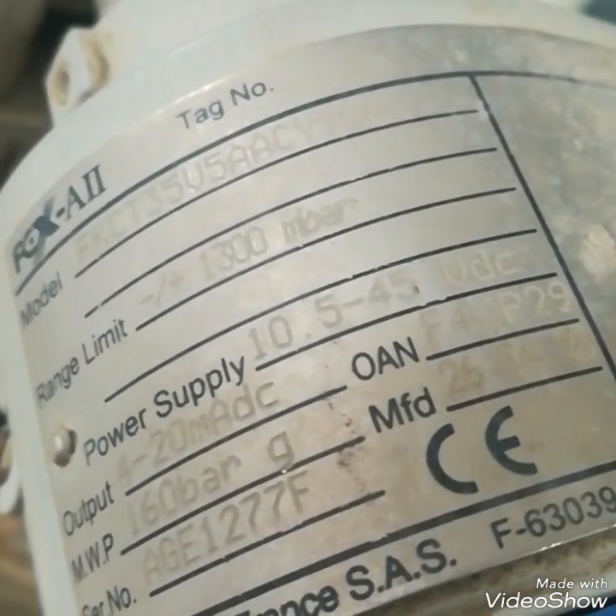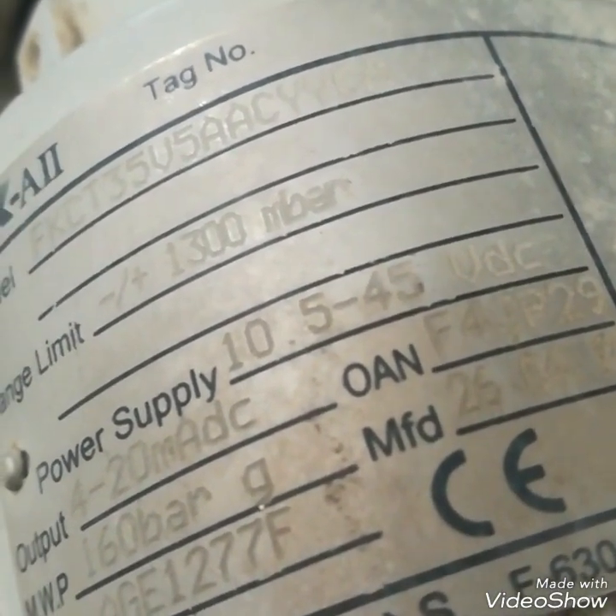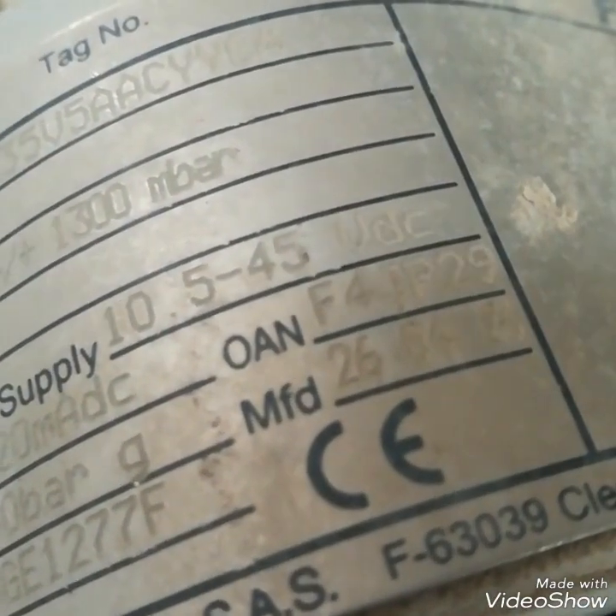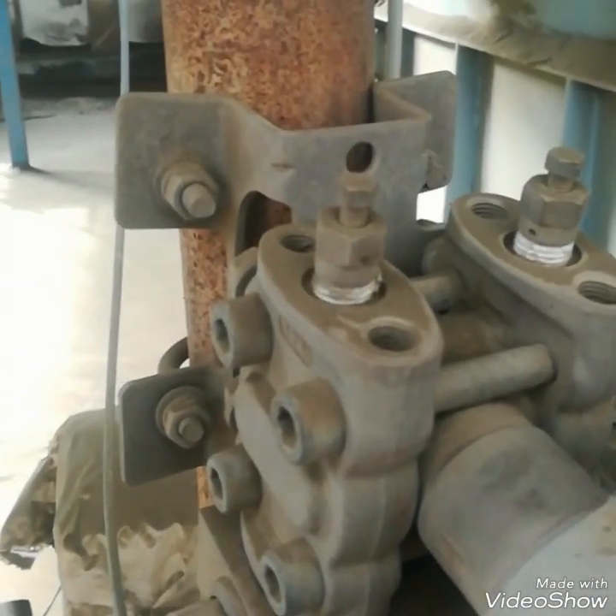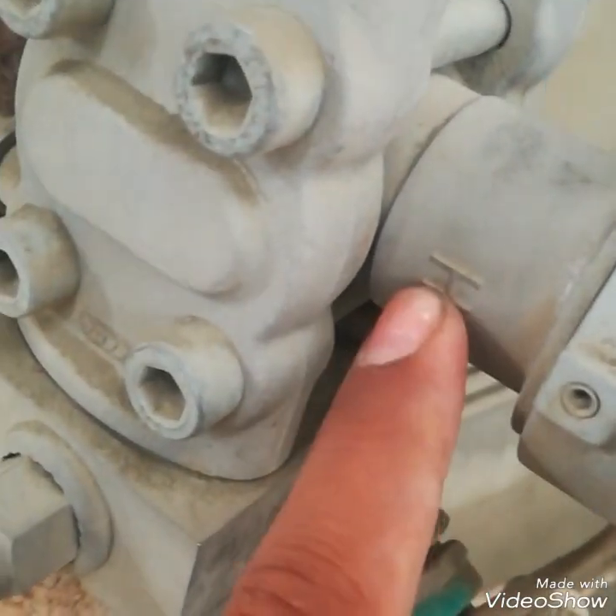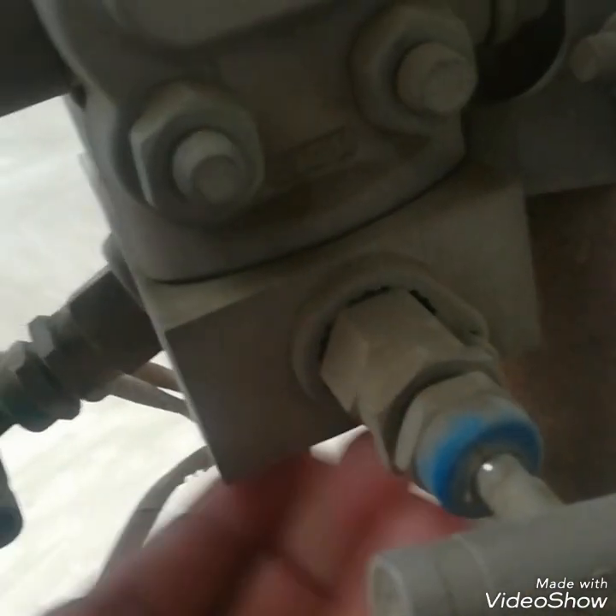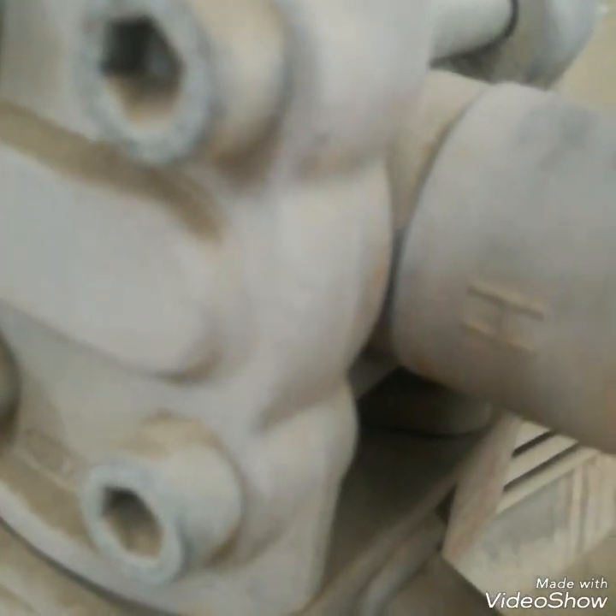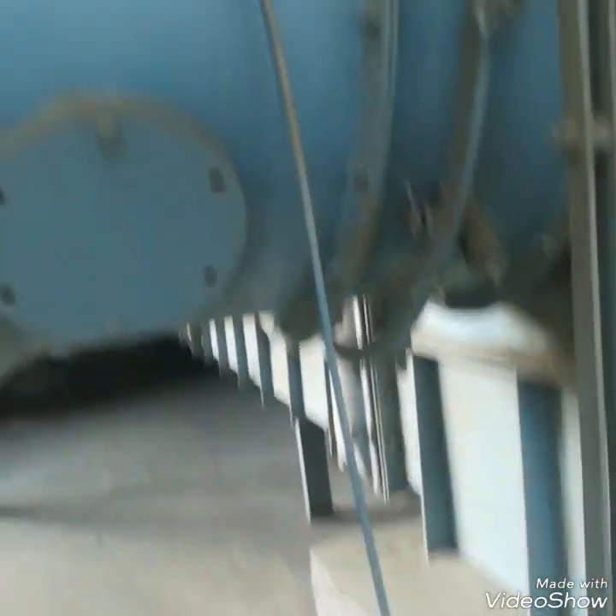This is a pressure transmitter — a Fuji pressure transmitter, FCX-AII model. You can see its nameplate: power supply 10 to 45V, and its range is 1300 millibar. It has two sides: H for high side and L for low side. It has a manifold with three valves — one for the high side, one for the low side, and one equalizing valve.